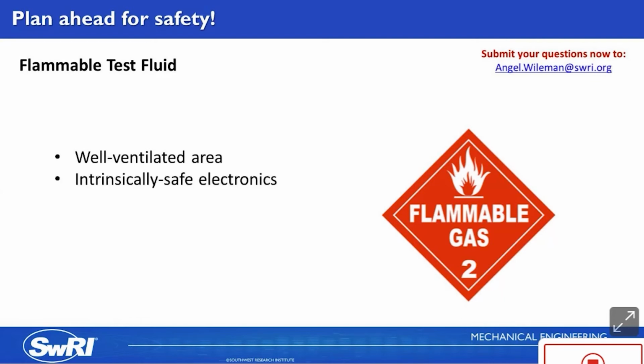Non-rated electronic devices should not be allowed within 15 feet of flammable gas and vapor sources. This includes cell phones, cameras, and non-rated instrumentation. All the electronics that are on the test stand must be approved as intrinsically safe with a minimum of Class 1 Division 2 hazardous area rating. This ensures the equipment will not produce sparks that could ignite the vapors.